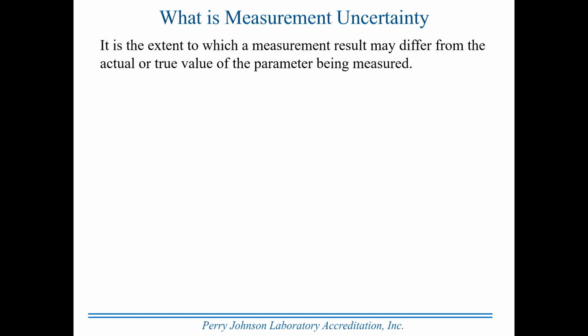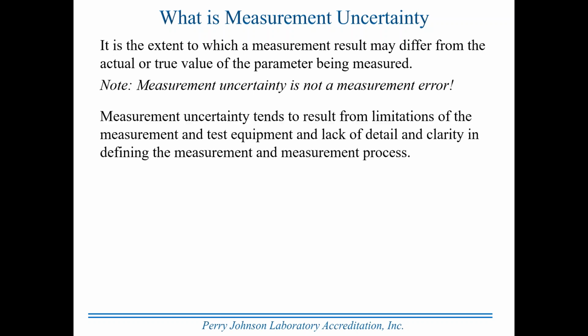Measurement uncertainty is, by definition, the extent to which a measurement result may differ from the actual or true value of the parameter being measured. Measurement uncertainty is not a measurement error. Keep that in mind, it is not a measurement error. And people used to talk about the uncertainty as the error in the measurement. And you were permitted to have no more than a particular amount of error in your measurements, or it would be out of specification. It typically does not occur in conversation with metrologists anymore because technically it's not correct. It's not an error in the measurement.